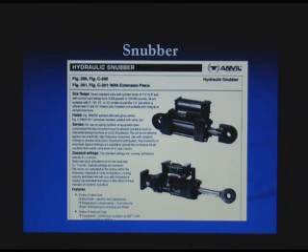These were mostly used in nuclear power plants, and if anybody has ever seen any picture of the inside construction of a nuclear power plant, they were using them everywhere, because if any earthquake comes along they don't want the pipe to move. Those plants are designed for high accelerations, up to 7G. San Onofre was designed up to 7G. And they were used quite often because you can't put guides everywhere. Due to the high temperatures, if you try to hold the pipe with a guide, your forces are tremendous.